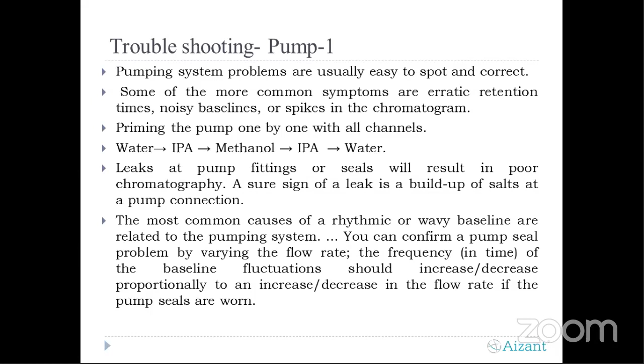Seals of the pumps are very crucial. If there is any leakage, it will show up as non-performance of the pump. And if you are using a lot of buffer mobile phase, you will find salt deposition at these seals. So we always have to prime and clean our system on a periodical basis. If the seal is gone, we should not deal with changing seals ourselves. If you have an instrumentation engineer, request him to rectify it once it is identified.